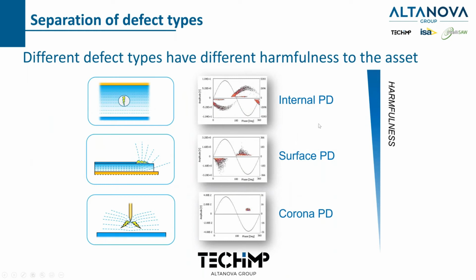So different types of partial discharge. Let's talk about those real briefly. So the first one, as you can see here, is internal partial discharge, which is basically cable insulation, and it is the most harmful type of partial discharge. And then we have tracking discharge, which happens on the surface, not quite as dangerous as internal. And then corona, which is more of a spark or an air gap discharge. It's the least harmful. Doesn't mean it's not harmful. It's just the least harmful out of these three. And then we have all these graphs here in the middle, which are called phase resolved discharge patterns, and we're going to talk about these. You'll understand them, but basically this helps us identify the types of PD, whether they're internal, surface, or corona.